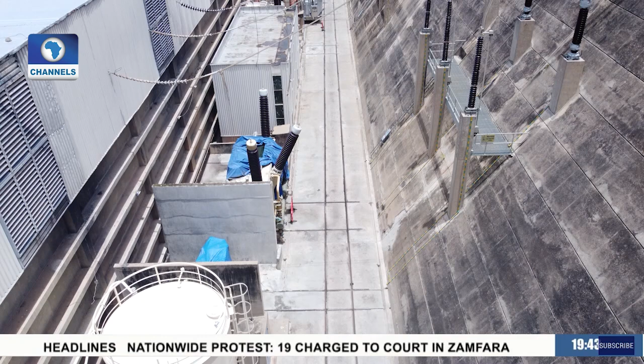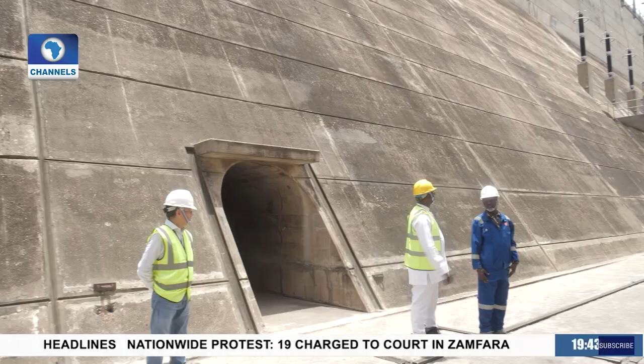This is a transformer deck, and we have two sets of transformers: the power transformers. This is where we transform the voltage from the 16 kV that comes out of the generator to a higher voltage of 330 kV that we take to the grid, to minimize losses.